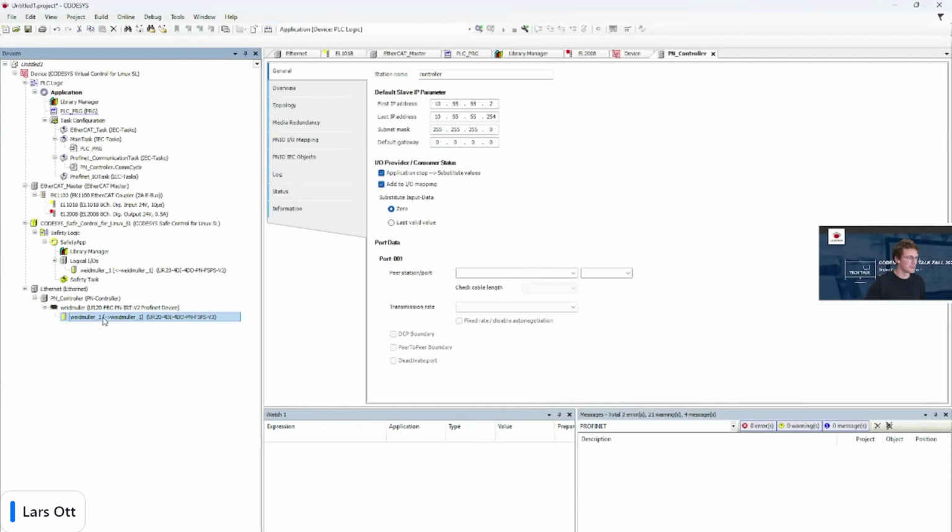And you will notice that in brackets here, it has this little arrow and then another Weidmüller one. And this is for our logical IO mapping. So we have our non-safe device tree here, and then we have our safe device tree that has this logical copy of the UR20 IO. That allows you to have full control over the non-safe part of the tree without affecting the safety application and changing CRCs and requiring recertification. So that's quite a nice feature.